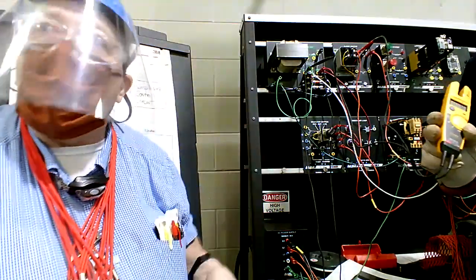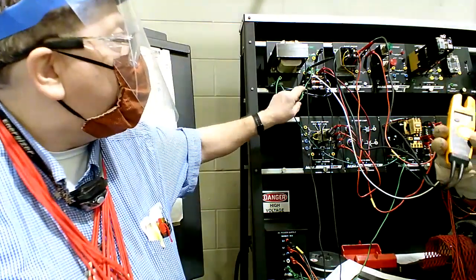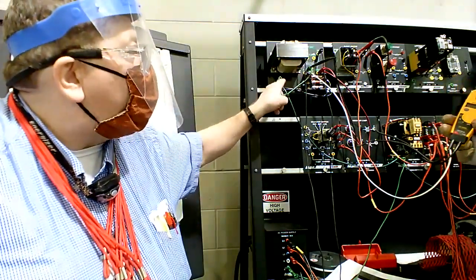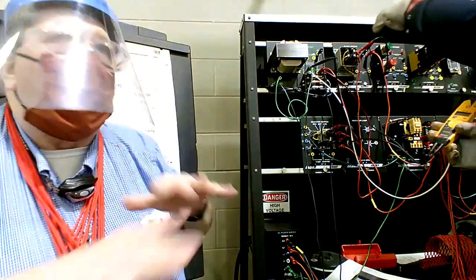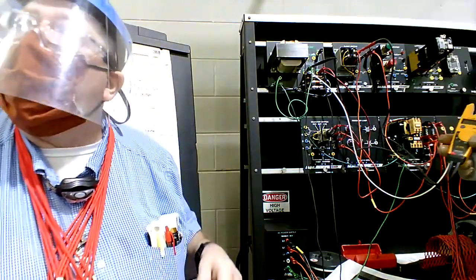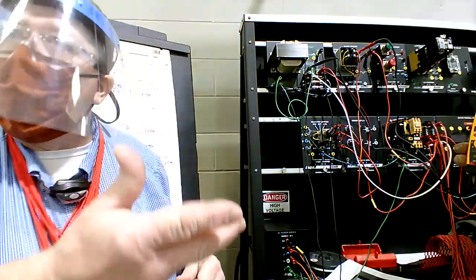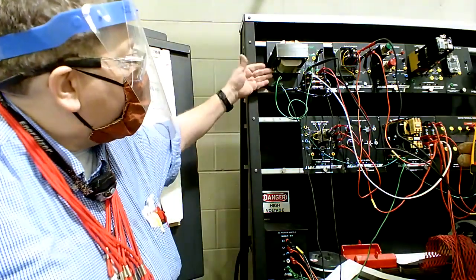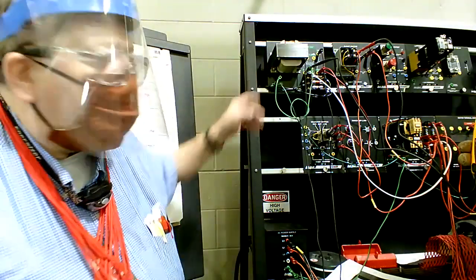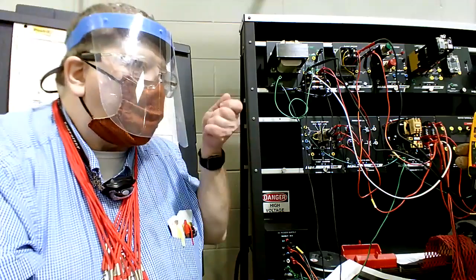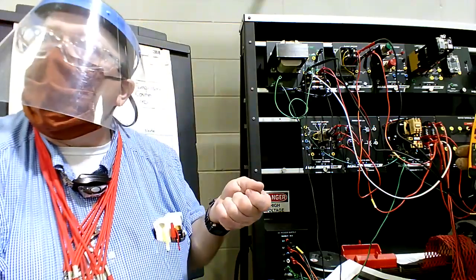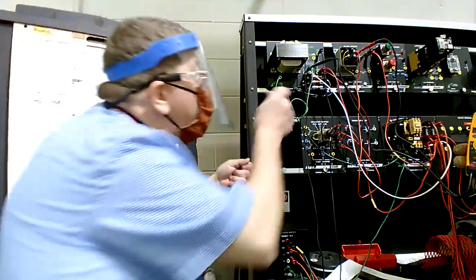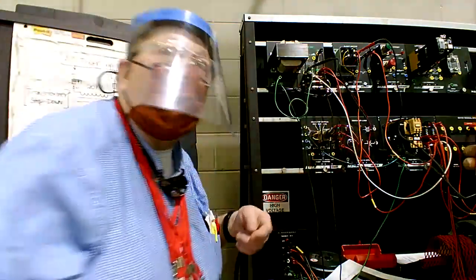So if you ever get in a panel, even though the neutral is grounded and you see a grounding jumper there, if you see rust in that panel, like on a hog farm or in a food processing plant, where the ground connection is, and you're using ground but getting some funky readings, then get off of the ground and go to the real neutral. Go to the real neutral for your reference point and use neutral as your 0 volt reference.